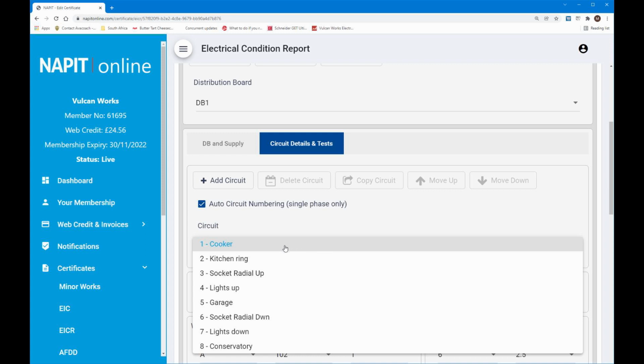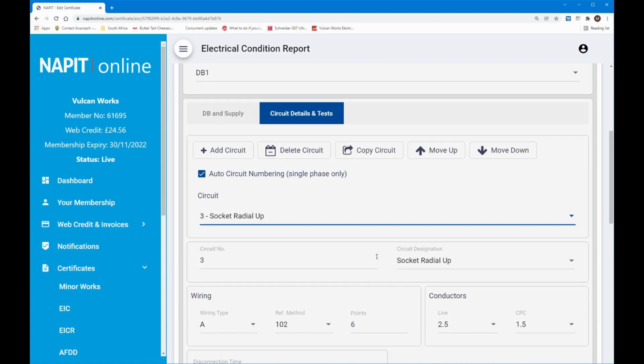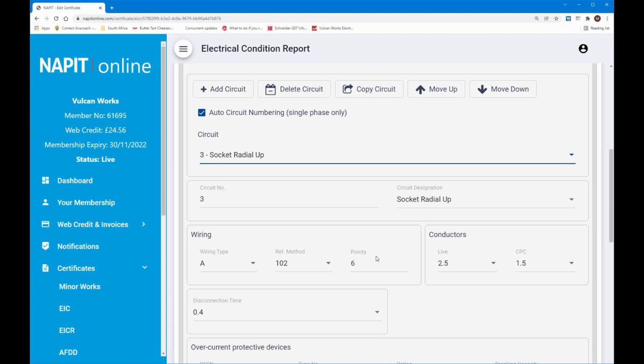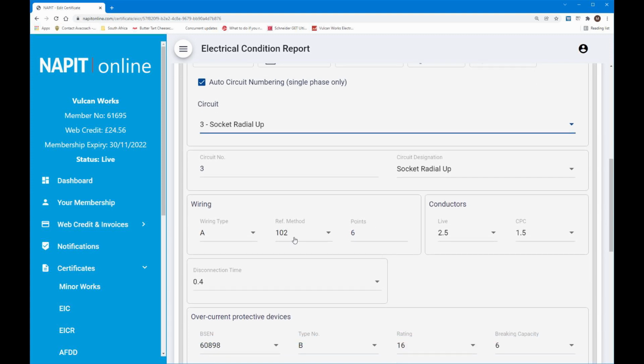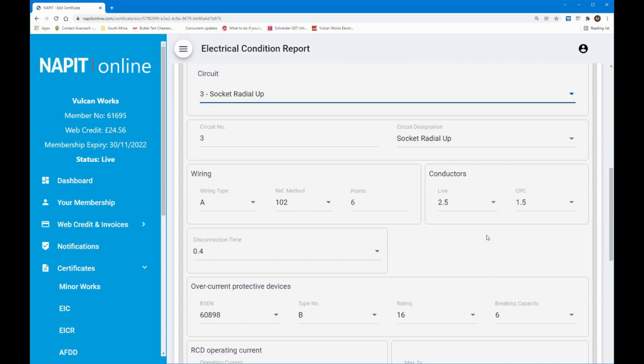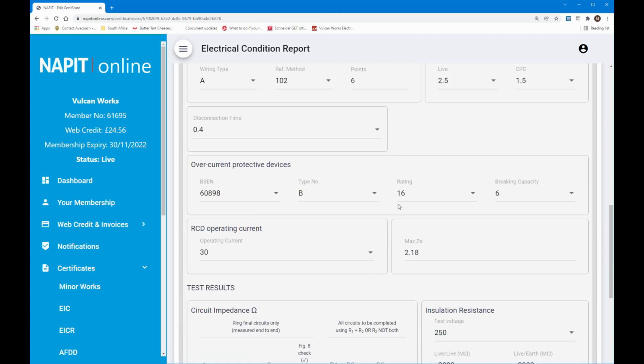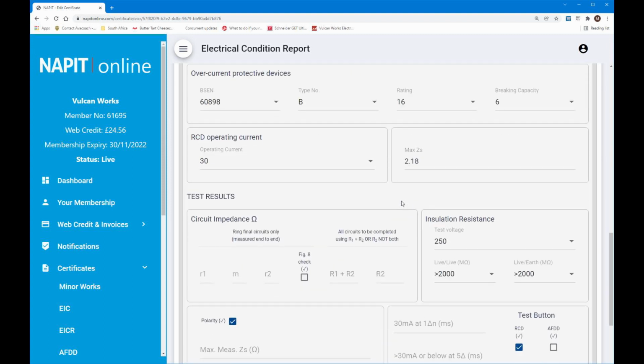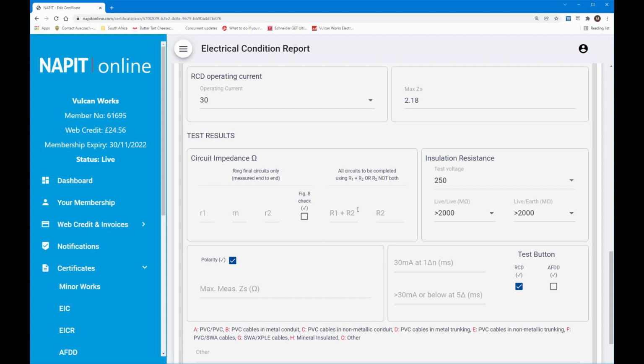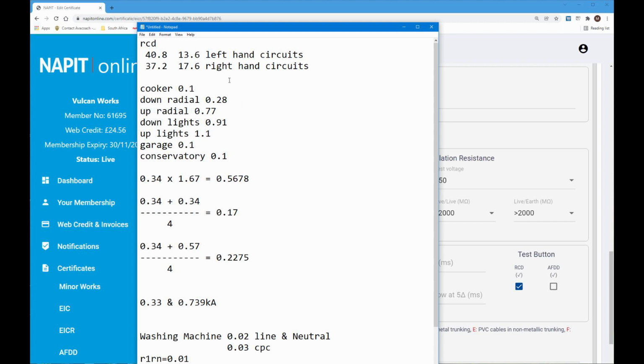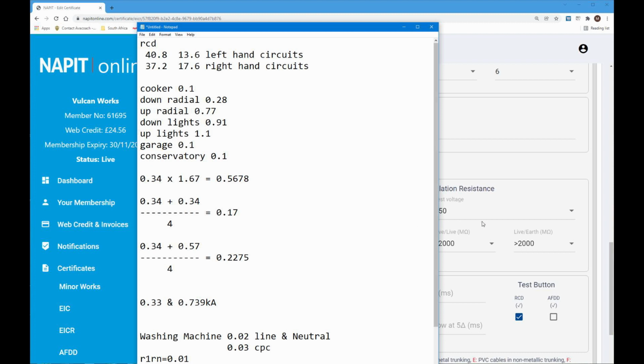Come to the rings, I'll come to the kitchen ring in a moment, because that's a little bit longer to do. So let's do the upstairs radial. So the upstairs radial, again, type A, 102. There are 6 points on this circuit, and this is 2.5, 1.5. Again, 0.4 disconnection time. It's a 16 amp B type MCB. And a 16 amp MCB has a maximum ZS of 2.18. It isn't a ring, it's a radial, and the result for that radial is, I'll just look it up. The upstairs radial gave me a reading of 0.77.